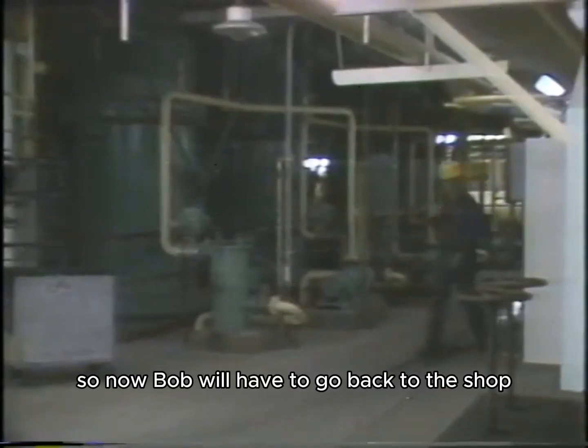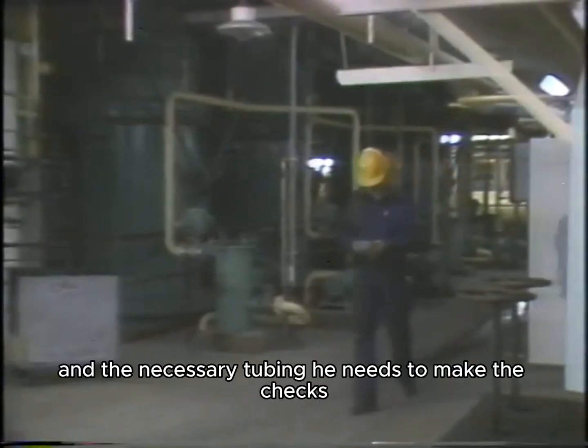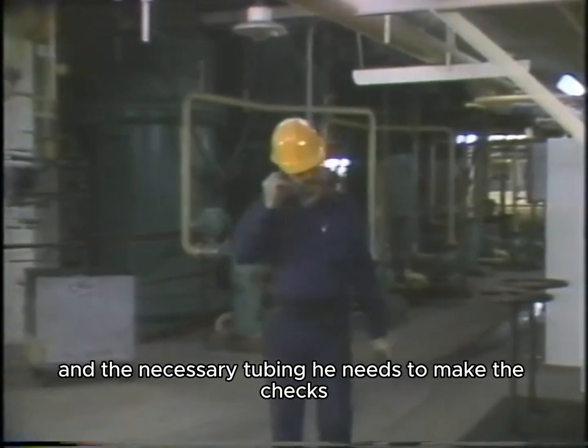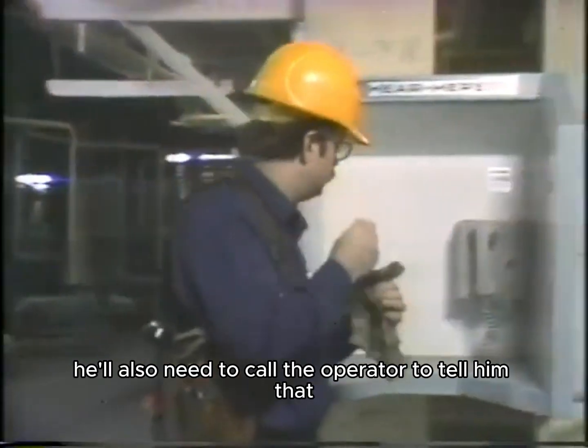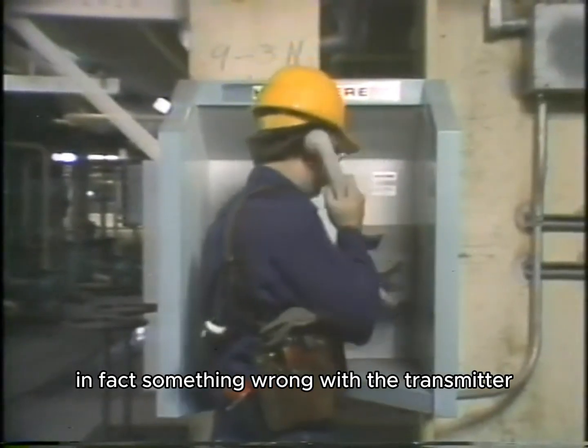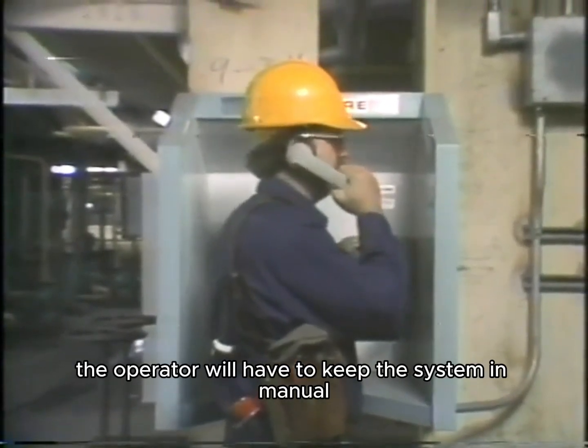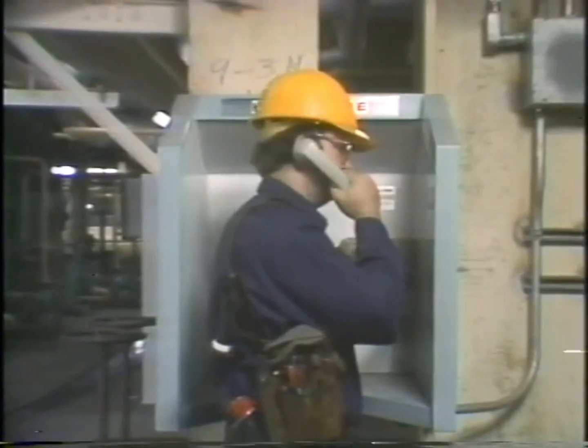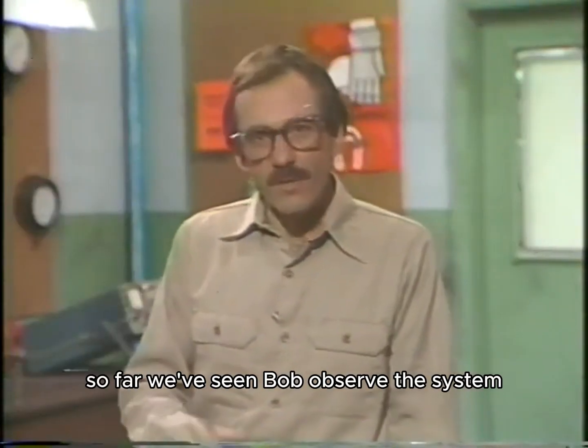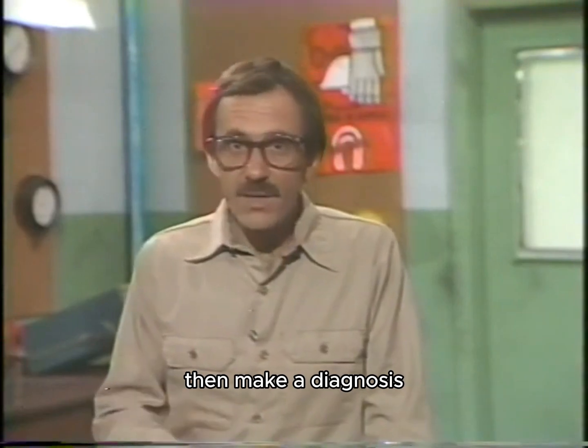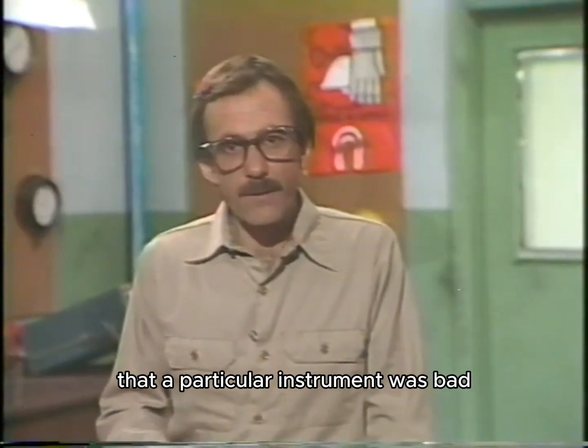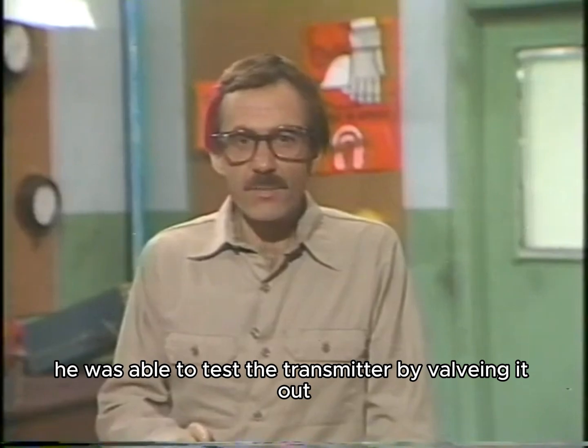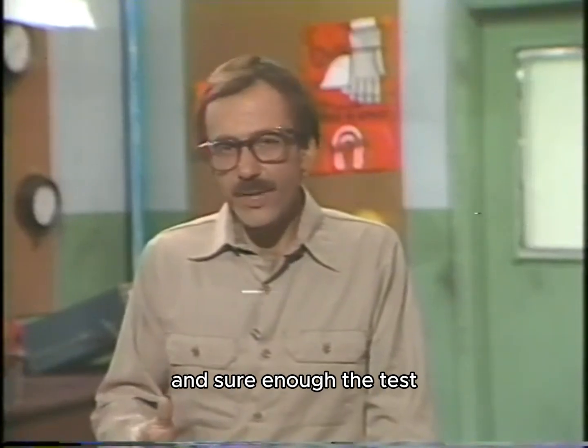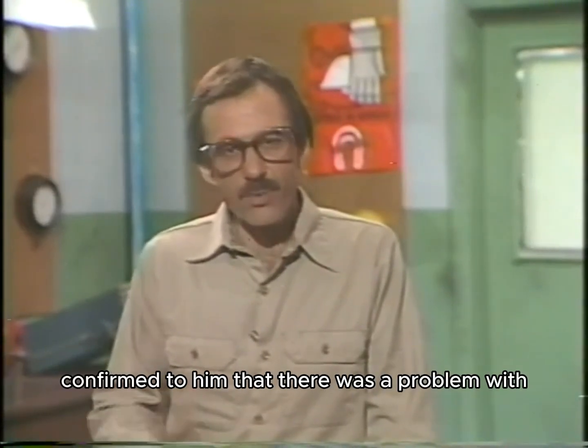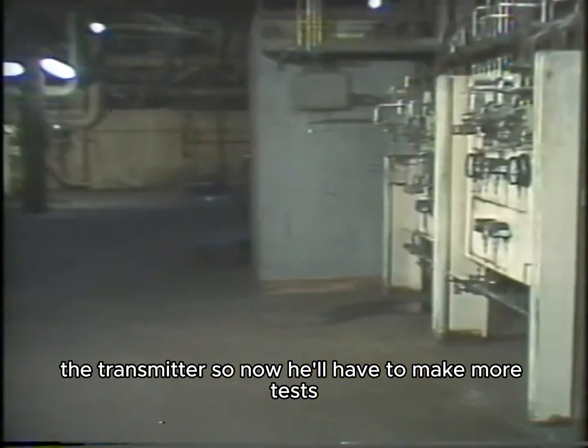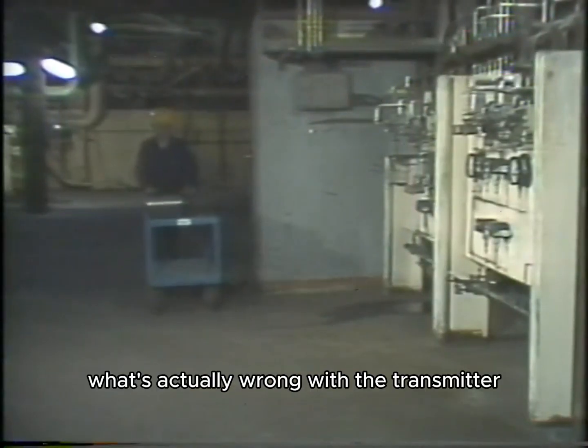So now, Bob will have to go back to the shop to pick up the calibrator and the necessary tubing he needs to make the checks. He'll also need to call the operator to tell him that there is, in fact, something wrong with the transmitter, and that the operator will have to keep the system in manual until the transmitter's fixed. So far, we've seen Bob observe the system, then make a diagnosis that a particular instrument was bad. He was able to test the transmitter by valving it out. And sure enough, the test confirmed to him that there was a problem with the transmitter. So now he'll have to make more tests to figure out what's actually wrong with the transmitter.